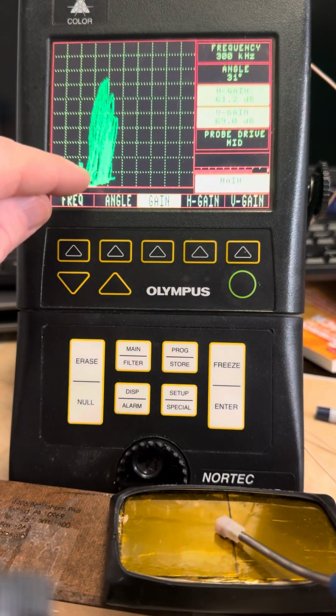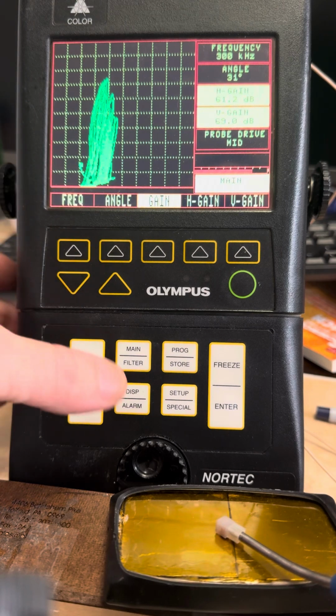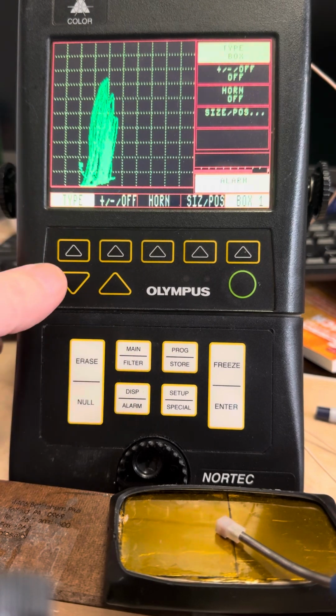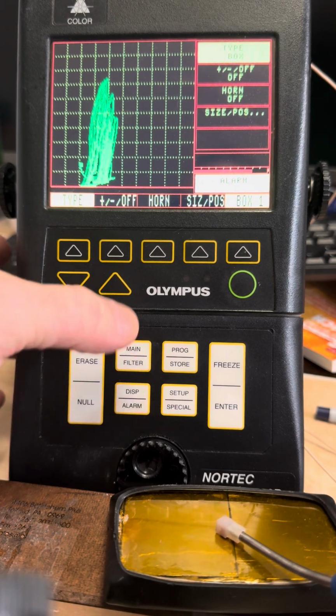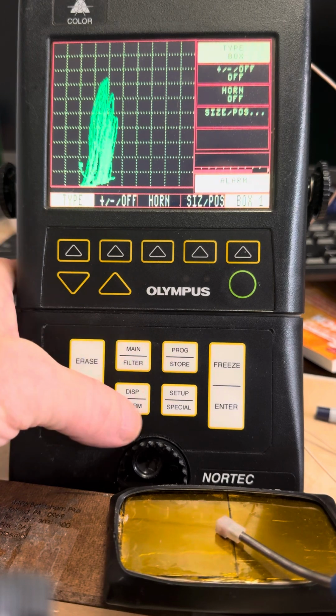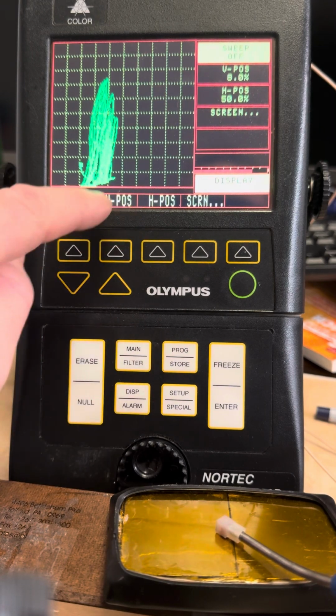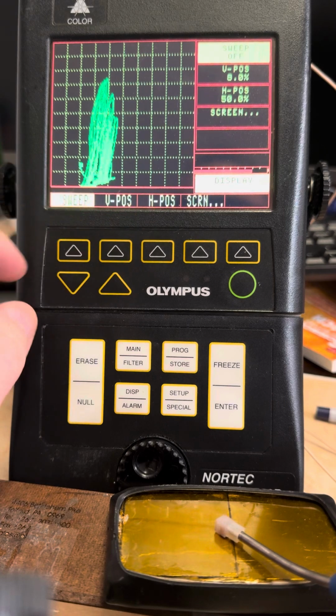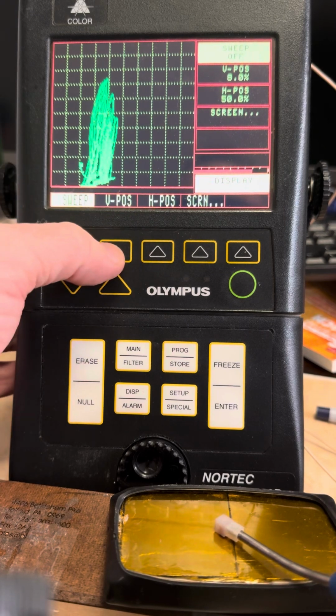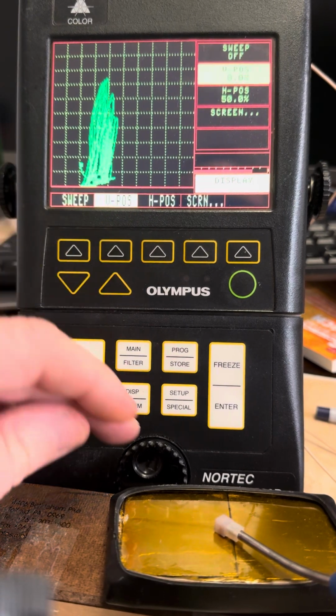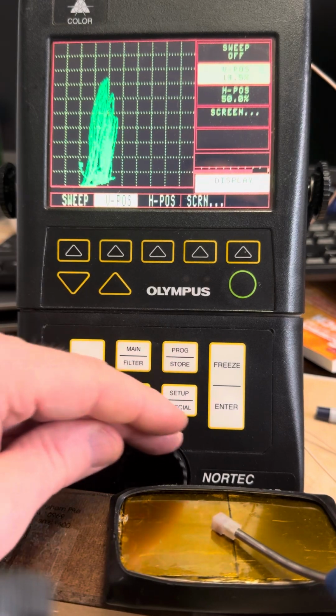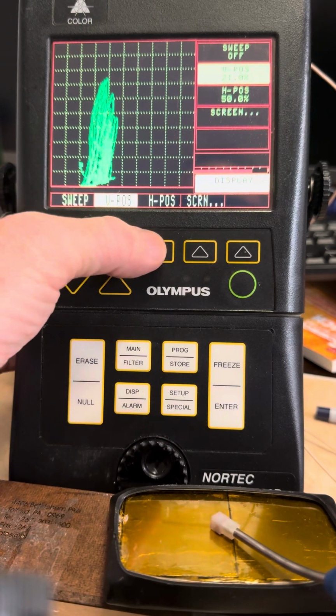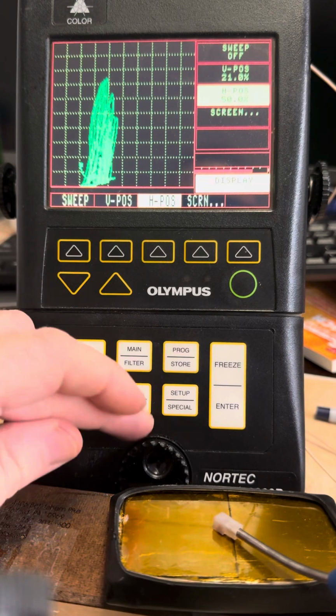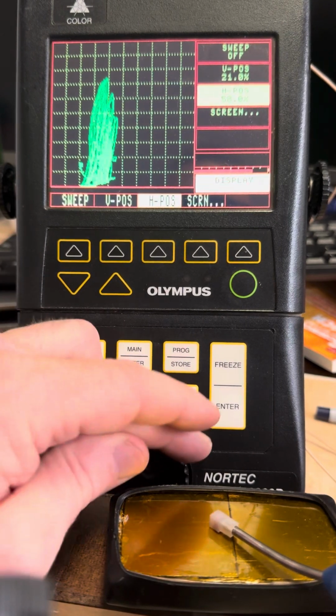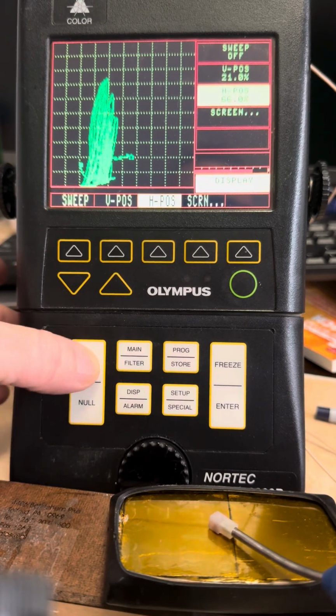Now, if I want to bring the null point up a little bit, I can go to display, and you've got to hit that twice because each one of these buttons has two sets of functions. So hit it twice, and you can change the vertical and horizontal position of that null point. So I'm just going to hit vertical and bring the null point up a little bit, and then I'll hit horizontal and bring it over to the right a little bit. I'll hit erase.